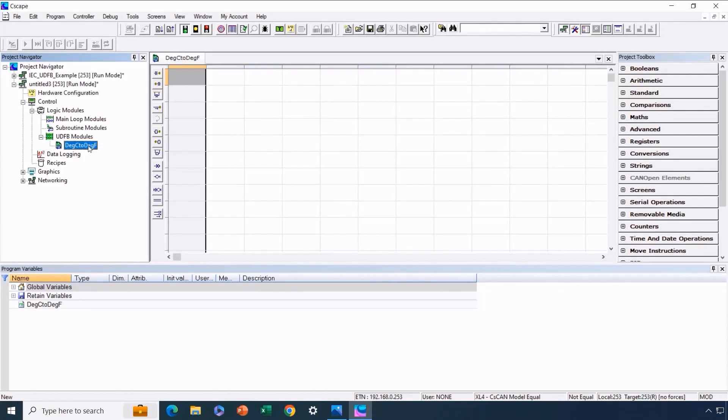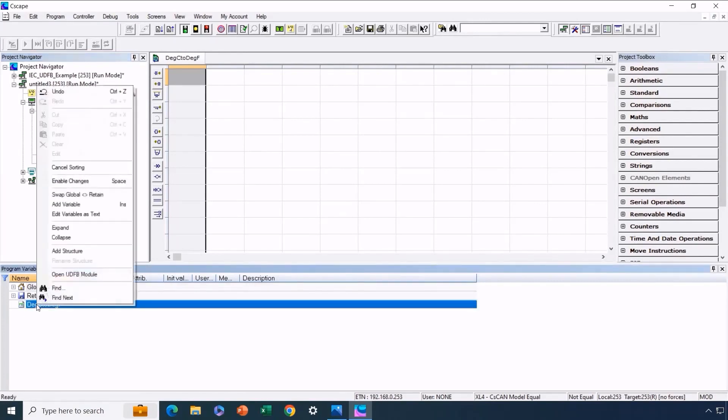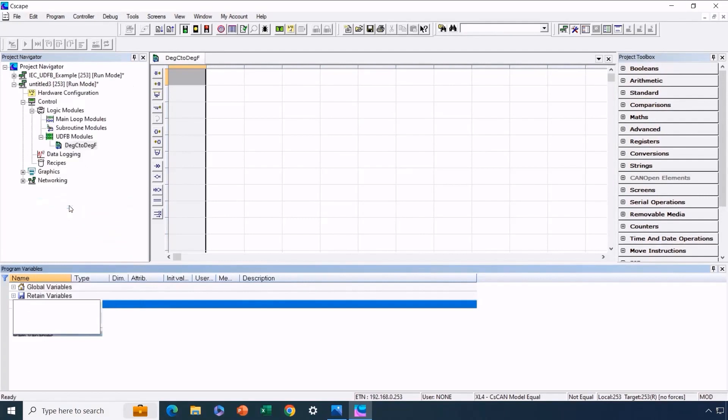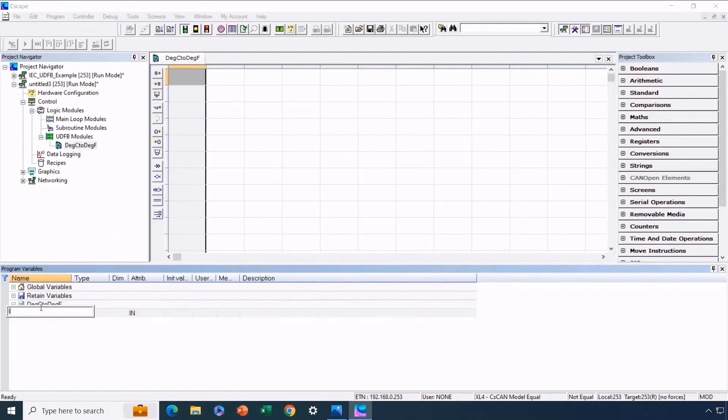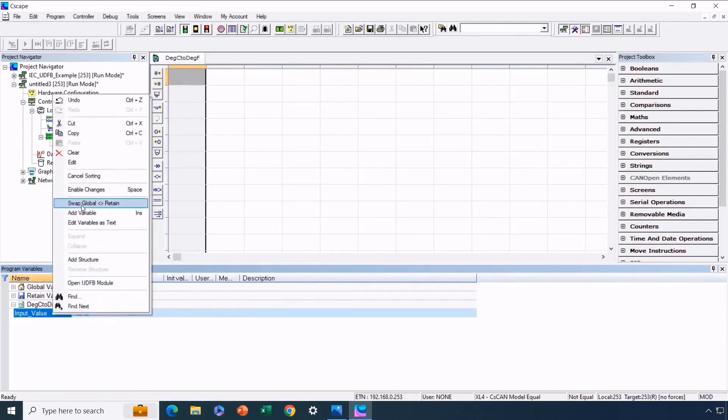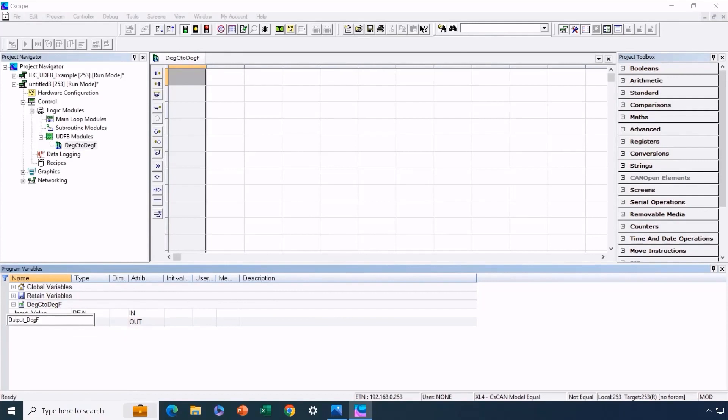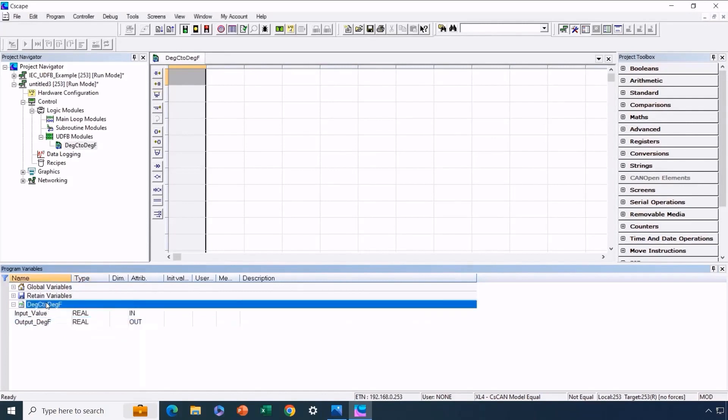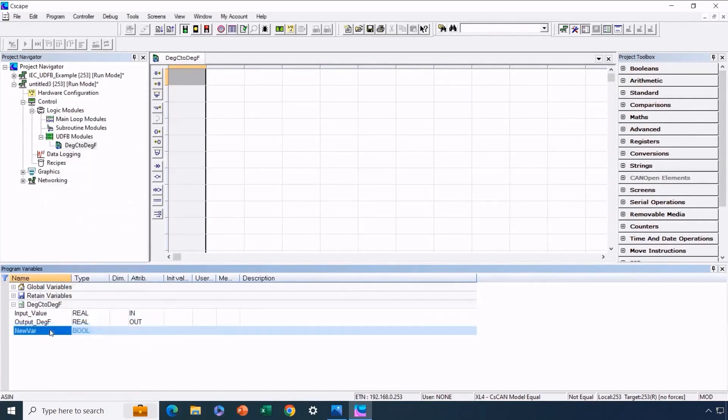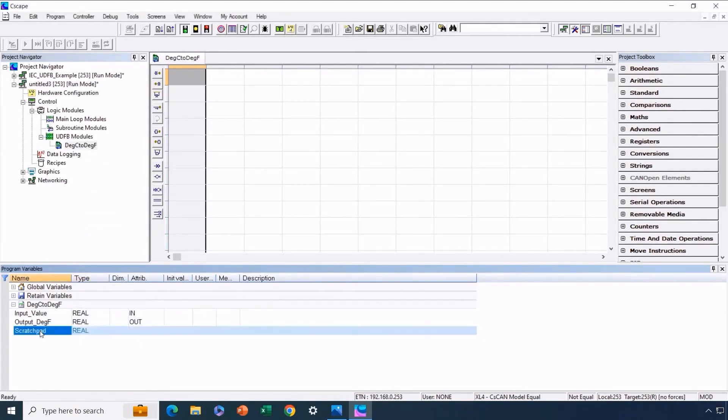The next task involves setting up necessary variables to make using the UDFB easy. You'll notice a new section in our program's variable window. We'll add the required variables here. In this case, we have an input variable named inputValue, specified as a real number, rather than a simple on-off choice. We also need an output parameter, which we'll call output degrees Fahrenheit. This one is also a floating point number. Now we'll add one last variable, our internal or private variable. This will also be a floating point value, and we'll name it scratchpad. So these are the variables we need to add.